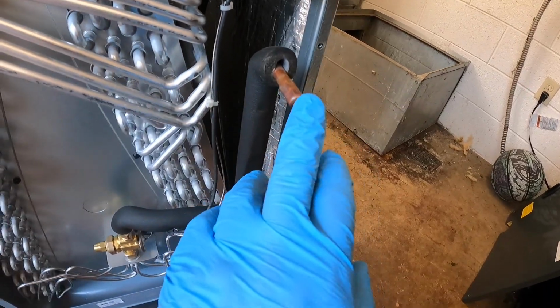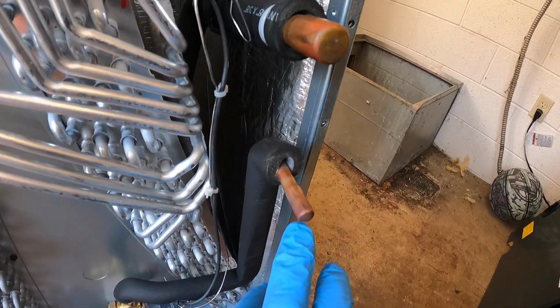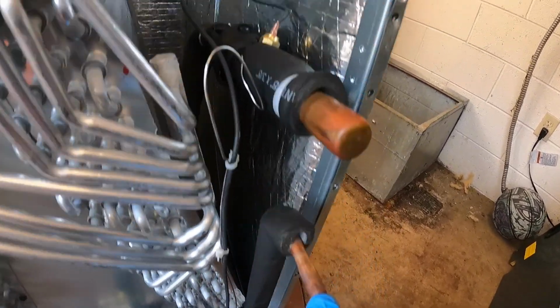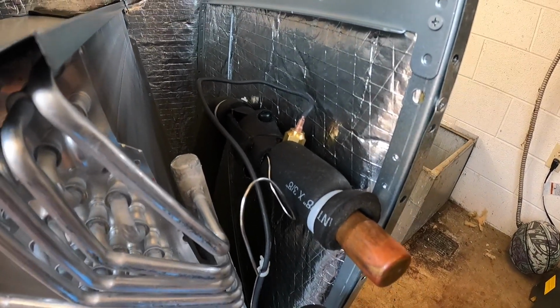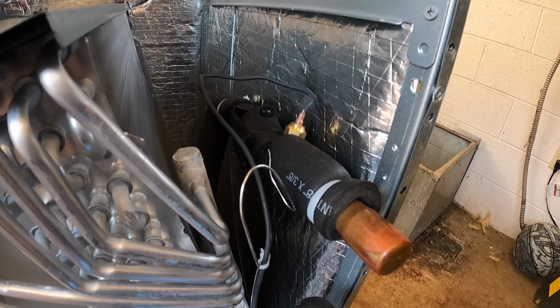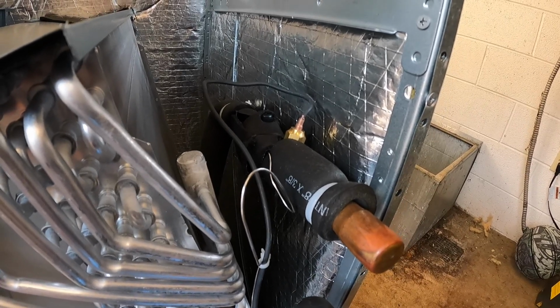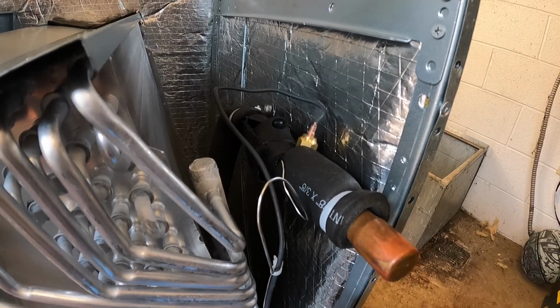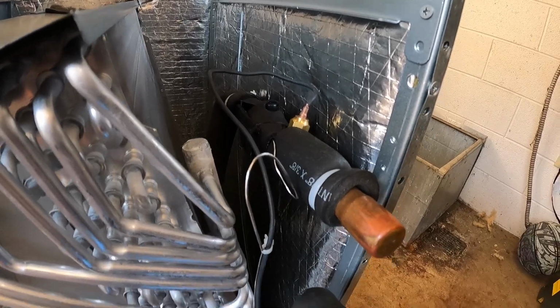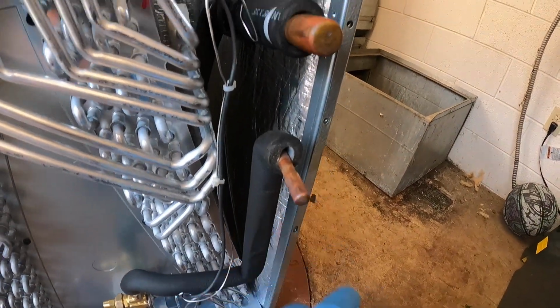I wondered, since they didn't have the Schrader here, what I would do about letting the pressure off before I cut it. But they've got an extra Schrader back there behind the TXV equalizer, looks like, so I can take that cap off and check it for charge and get rid of whatever's on it right now before I cut the spun copper off the end.